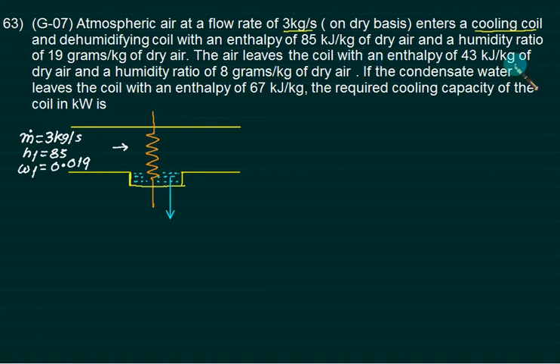The air leaves the coil with enthalpy H2 equal to 43 kilojoules per kg and W equals 0.008. The condensate water leaves the coil with enthalpy 67 kJ/kg. We want to find out the cooling capacity of coil. Cooling capacity of the coil is the external heat you have to remove from this.